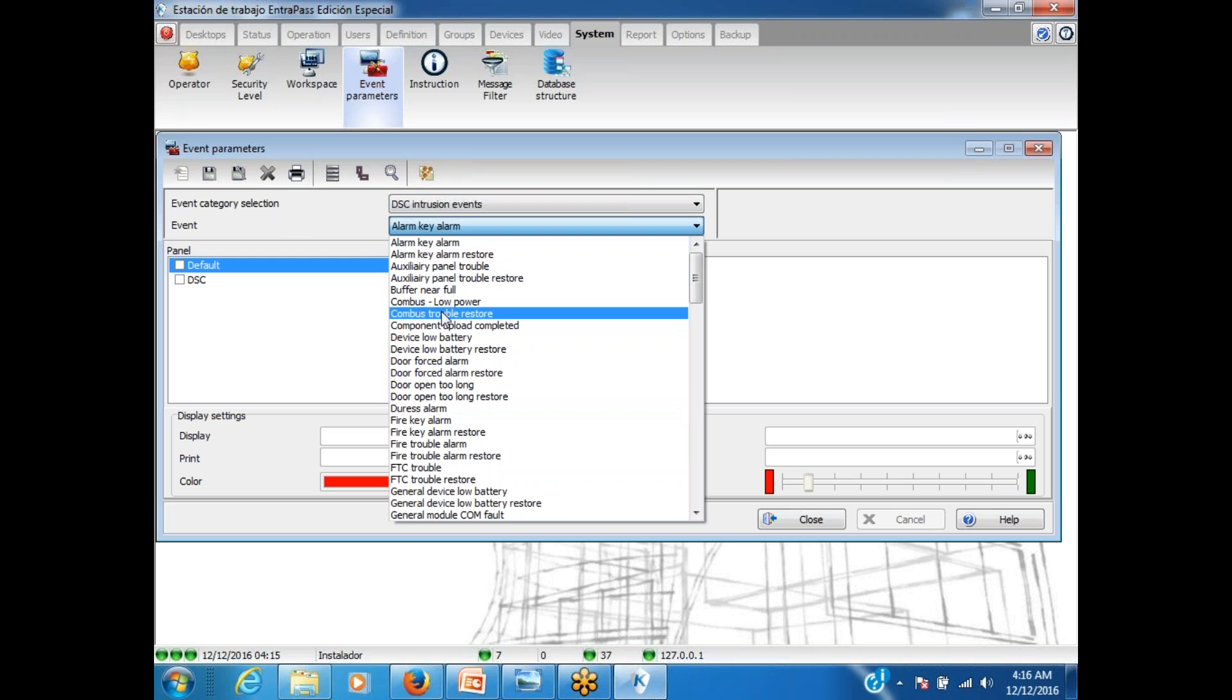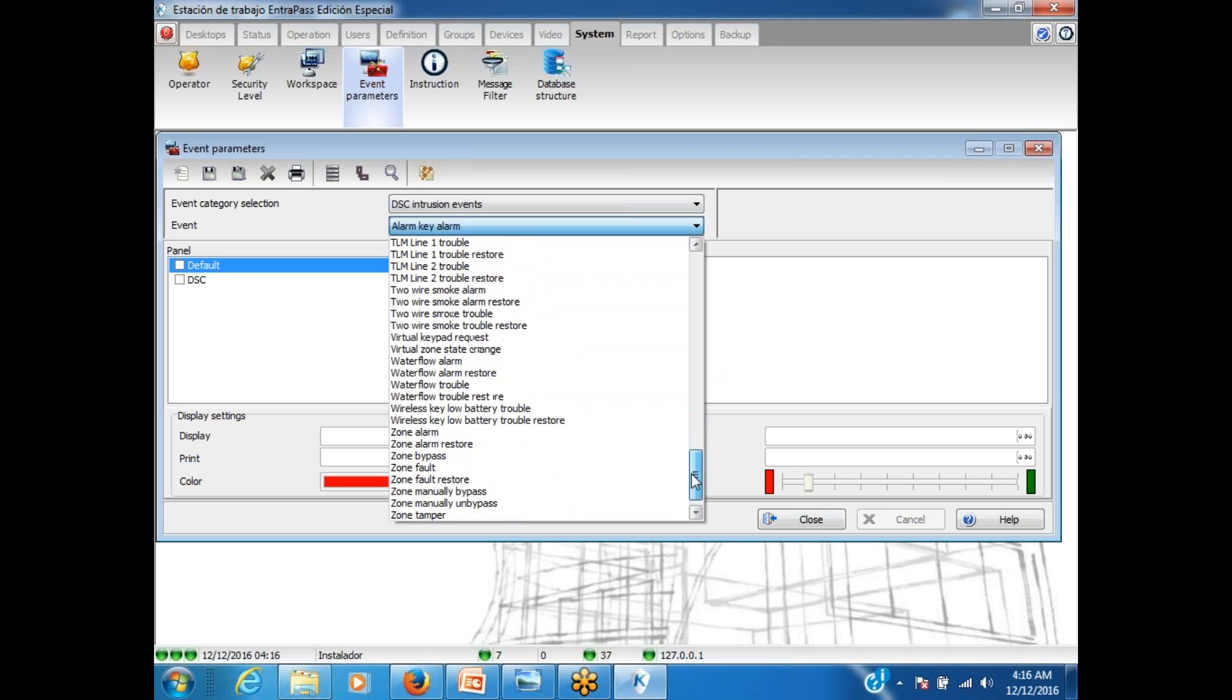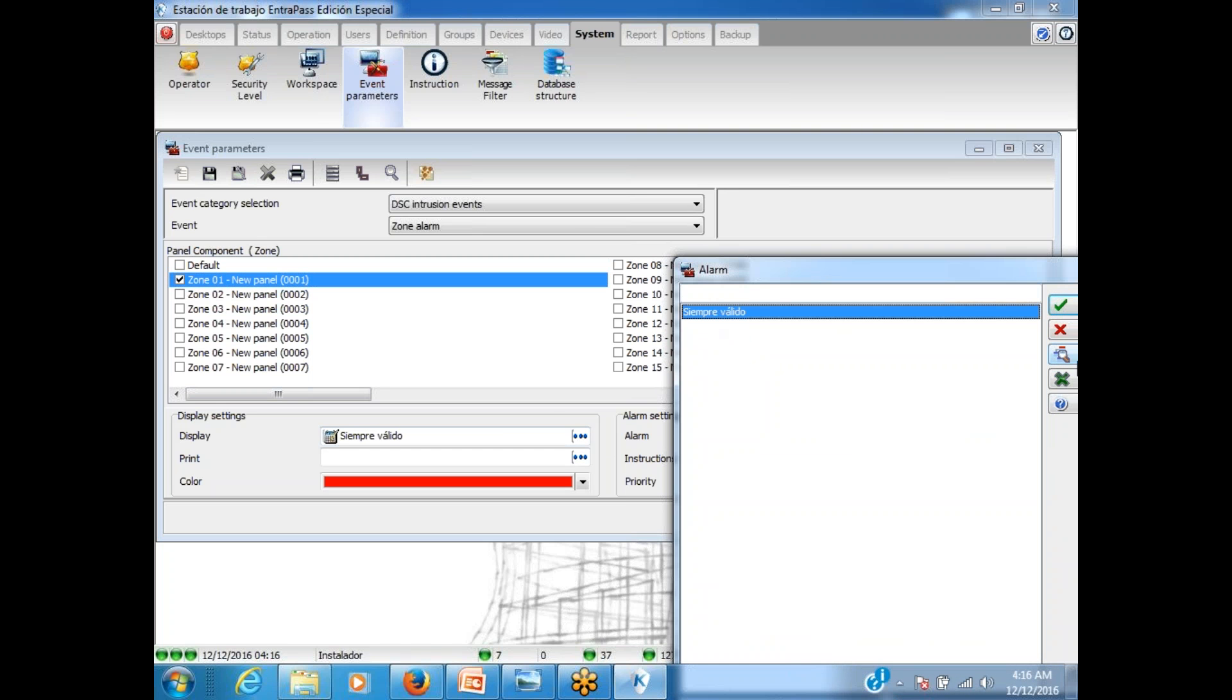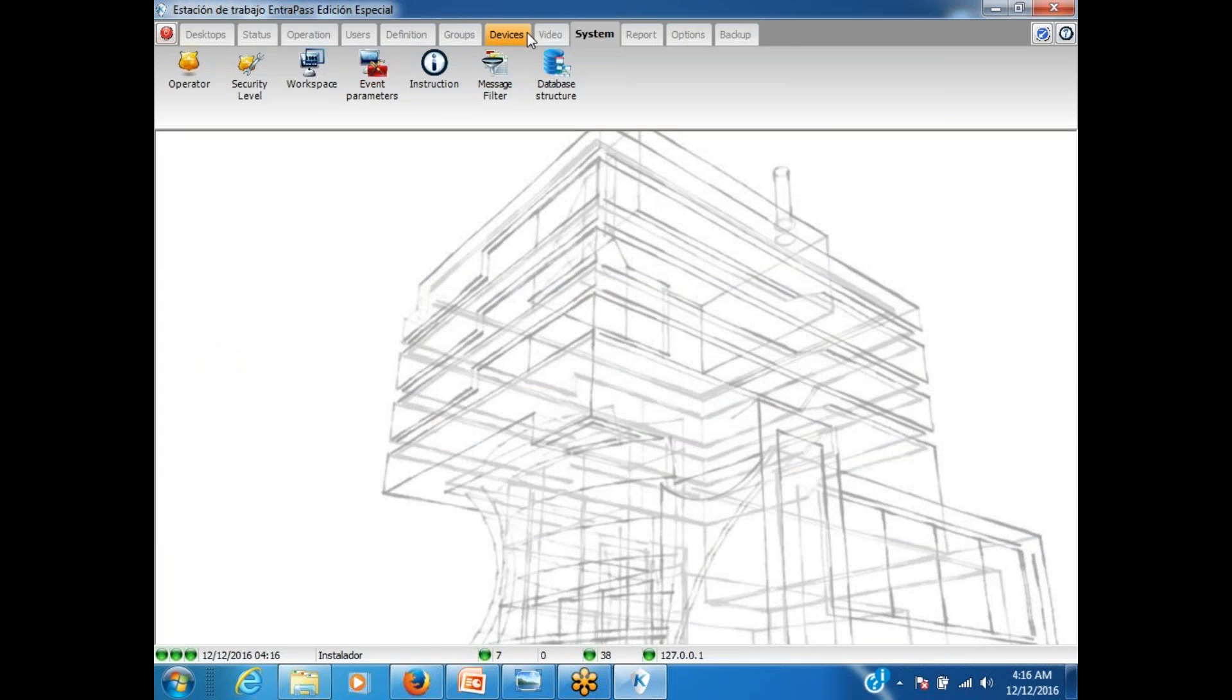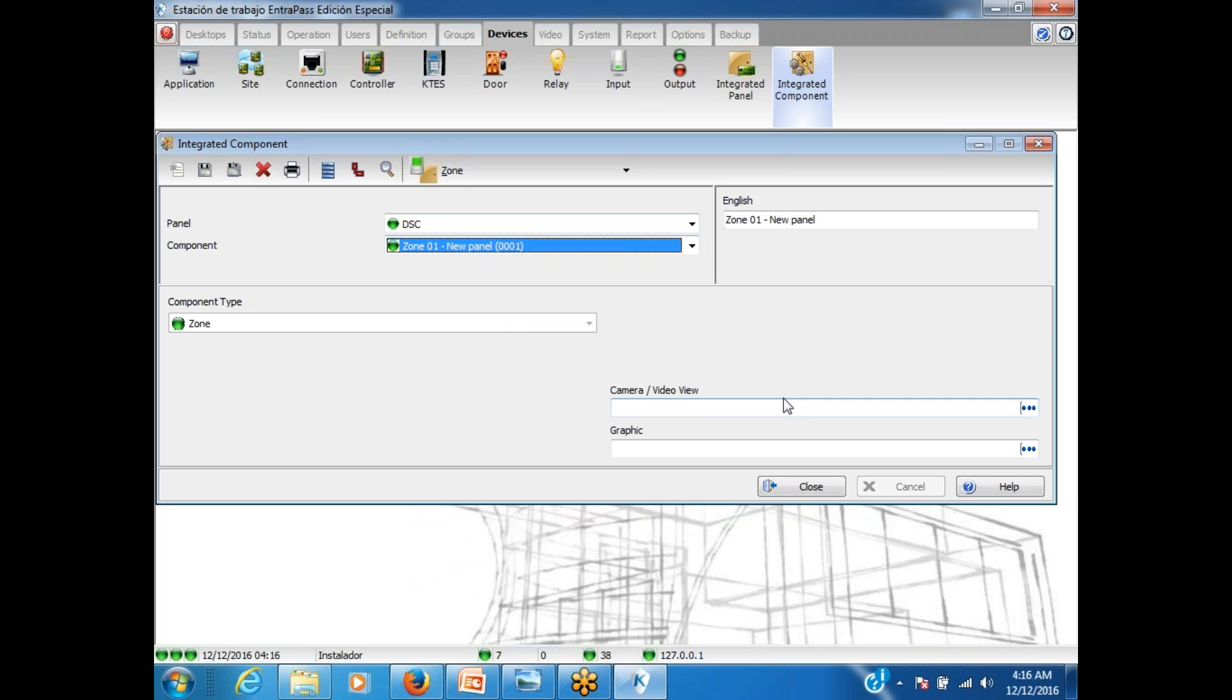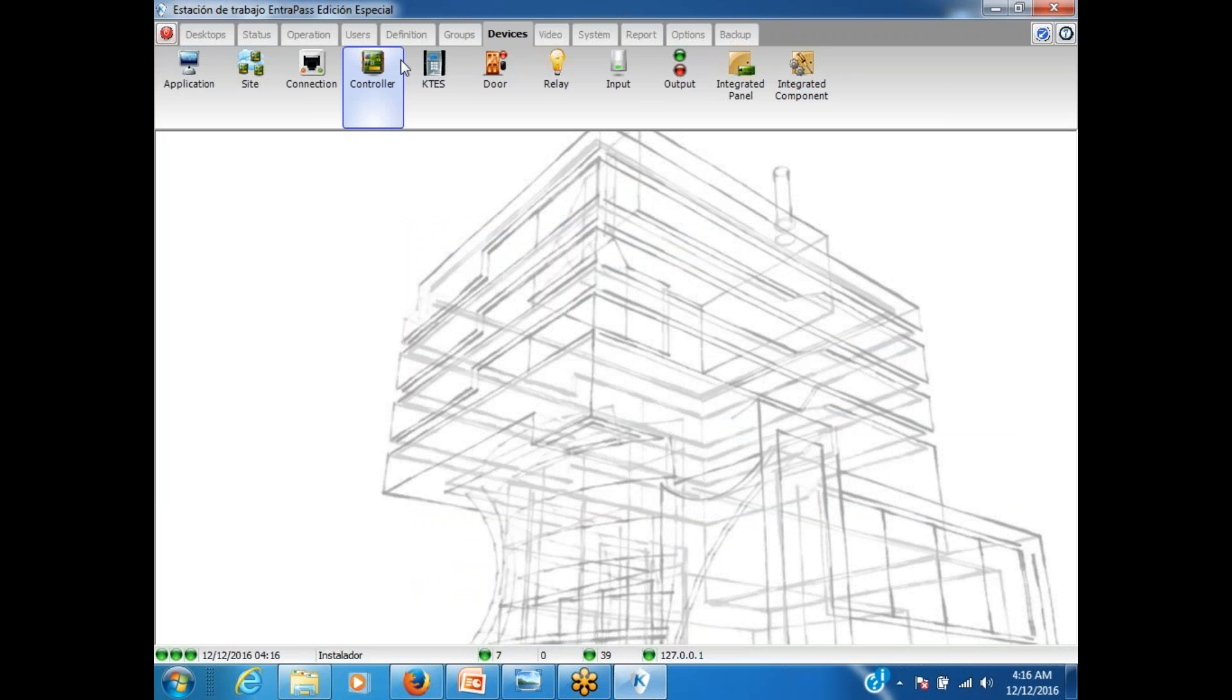Let's say, if I want on, if I have a zone in alarm in DSC. I can pop up the camera. Of course, I will have to. Here, I select zone one. Remember what I did for the door before? I have to do the same thing. I'm going to go devices. I'm going to select zone. Zone one. All right. And I will link the camera. So, the camera we have at zone one. So, whenever that zone one is in alarm, I will have a pop up. The camera will pop up and I can see.